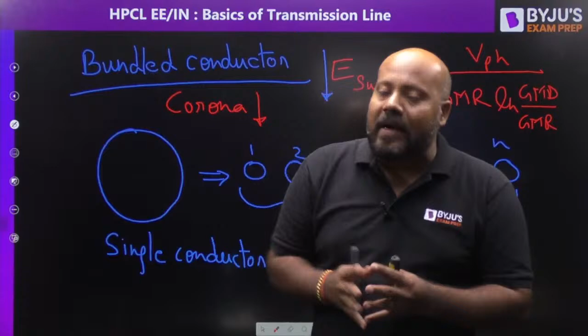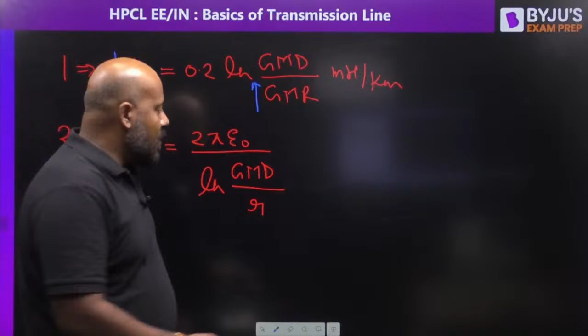The first thing is, if you see the inductance, it is given as 0.2 ln GMD upon GMR millihenry per kilometer. Now you are saying, sir, GMR has been increased, so inductance is going to be reduced. If you see the capacitance, we are defining it as 2 pi epsilon naught upon ln GMD upon R. Now we are not writing GMR here. Why? Because the GMR concept is not applicable in case of capacitance calculation. Why?